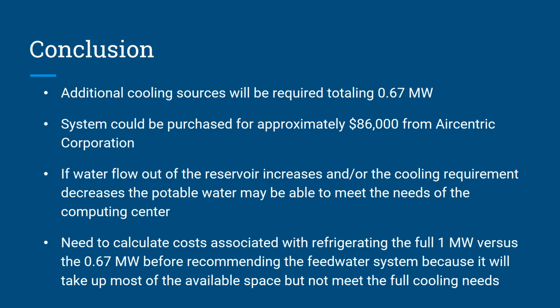Even though this system was maximized for cooling capacity, there is still 2/3 of a megawatt of cooling required for the computing center. The system is relatively expensive at $86,000 and takes up the entire space allowed. The MSU Office of Infrastructure Planning and Facilities needs to determine if this is appropriate for the cooling needs. If the computing center cuts the cooling requirement or more water leaves the reservoir, this system should be reevaluated.